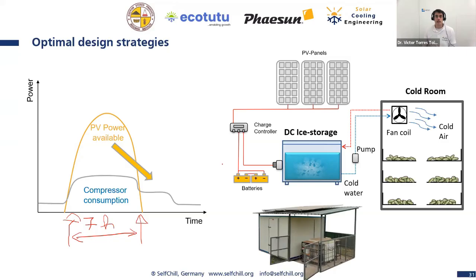This is a very interesting strategy that we follow, because the batteries are only there to store the surplus of the day and to extend the hours of operation of the compressors, of the heat pumps, of the cooling units. For doing this, we decrease the speed of the compressor so that we can run even more efficiently, and we can extend the operation up to 7 hours more. It could also be more, but normally our systems are working between 14 and 16 hours per day.